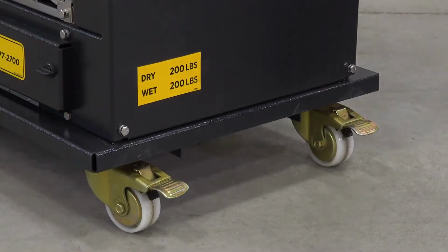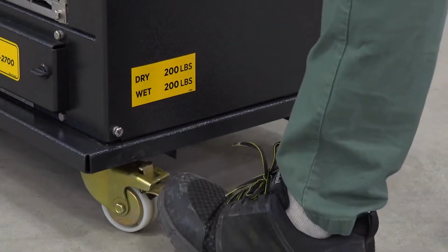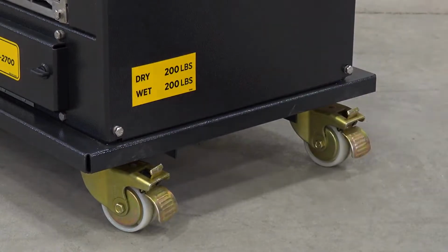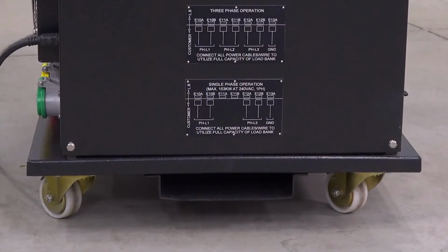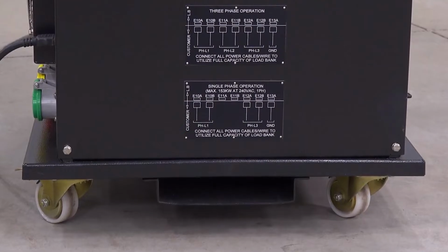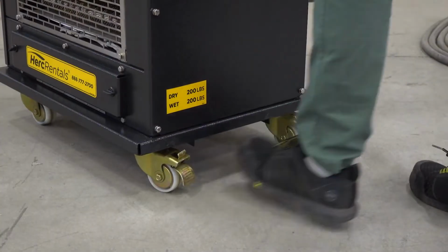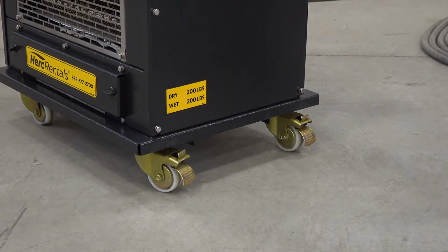When transporting portable load banks, which have casters, it is important to lock the casters. Smaller units have casters, larger units have casters and forklift pockets. During transport, load banks with casters should always be in the locked position.